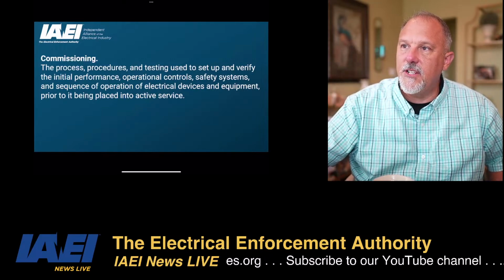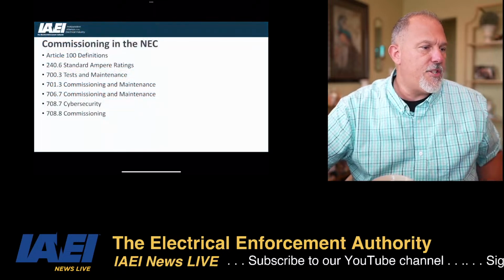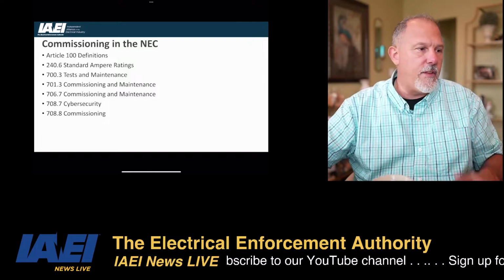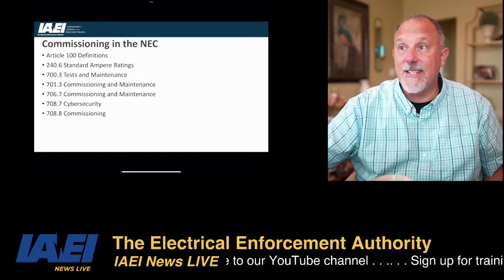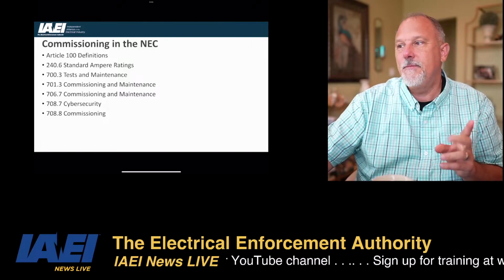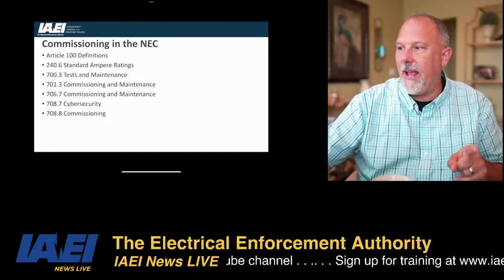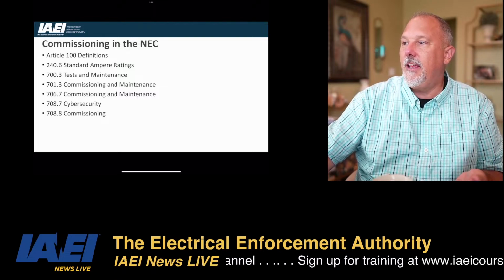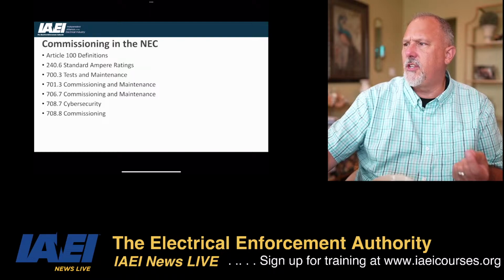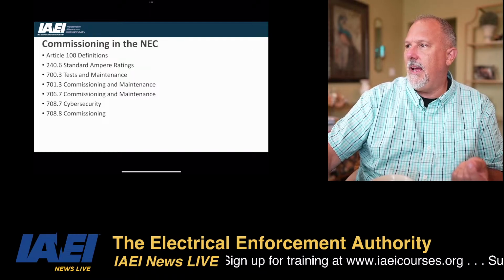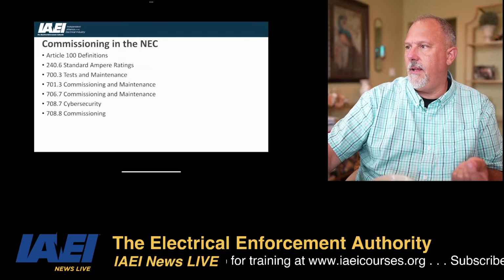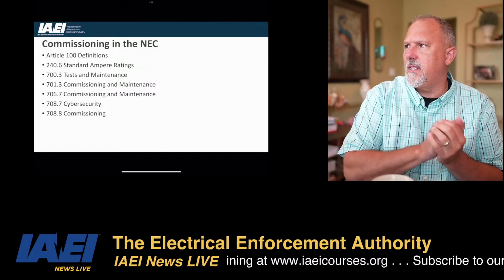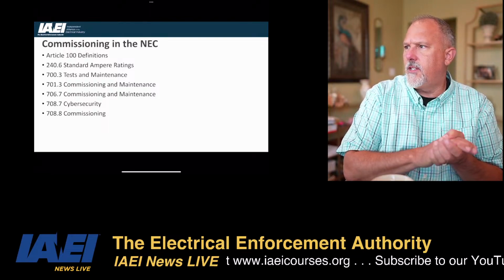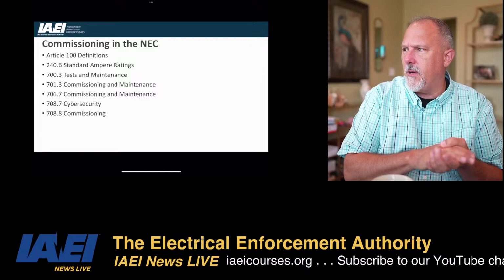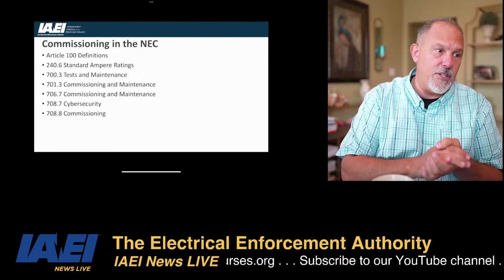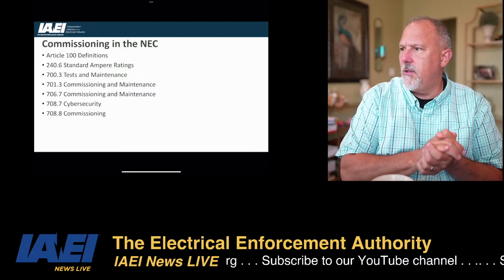Now, commissioning, if I did a search through the code, is used in these areas. Obviously you have the definition. We use it in 240.6, that's your standard ampere rating. And we use the term commissioning in relationship to cybersecurity, I believe. I say that, and I want to make sure that I am accurate. (D), remotely accessible: the circuit breaker, a cybersecurity assessment of the network is completed. Documentation of the assessment and certification shall be made available to those. Okay, it's not used there.